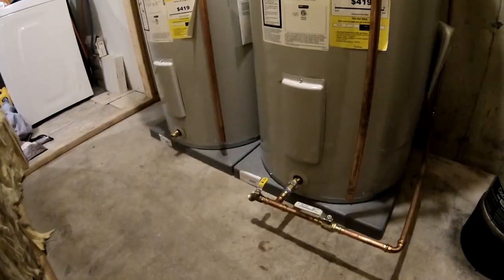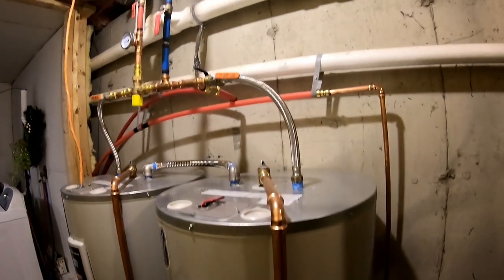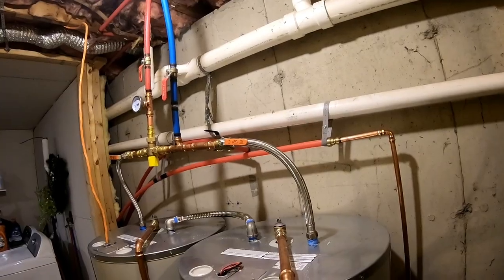One is a traditionally connected electric hot water heater. The second acts as a preheater for the first. The geothermal heat pump passes extra heat from the heat pump to the preheater, bringing the water temperature up from ground temp. This results in the electric hot water heater not having to work as hard to get the hot water to the desired temperature, saving us about 30% on our hot water costs.